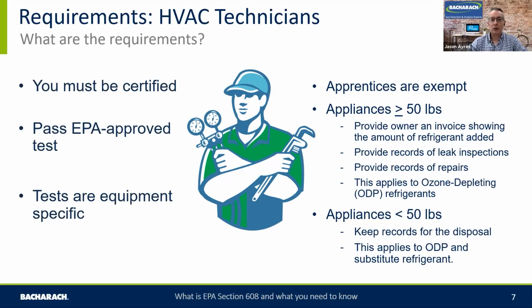Even though EPA 608 is really focused on assets and appliances over 50 pounds, if you are disposing of appliances under 50 pounds that have ozone depleting refrigerants, class 1 and class 2, and substitutes, you as a technician need to keep those records as well. So that's a broad summary of what the technician's requirements are for EPA 608.